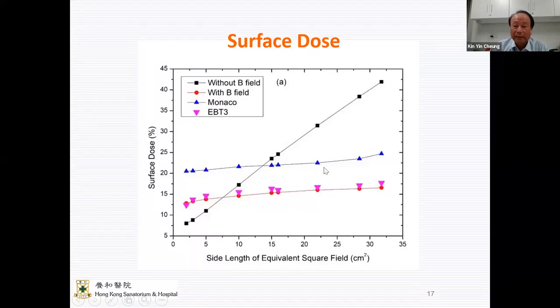The blue line with triangular blue dots is the computer calculation. There is a slight difference, a few percent, between measurement and calculation. We are trying to figure out the reason for the discrepancy. And the black line is the surface dose of the same Linac without magnetic field. So the surface dose is much more compared with the MR Linac.